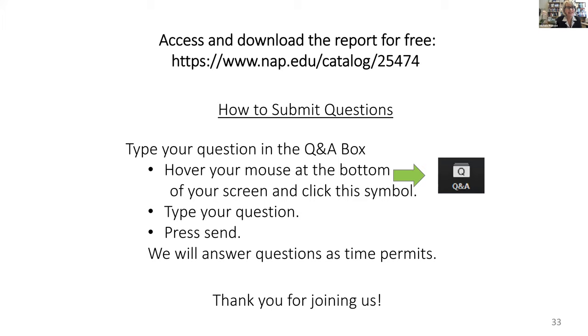Yes, this trade-off between scalding and the control of Legionella was discussed abundantly within the committee. As I mentioned previously, we looked at abundant data showing the benefits of elevated temperatures to control Legionella in all kinds of large buildings. More importantly, we came across documented evidence that when temperature control was relaxed to conserve energy, several of the problems came back, and temperatures had to be increased again.